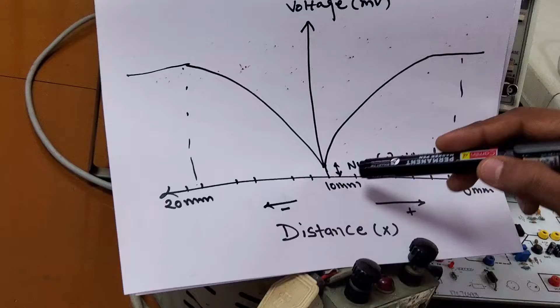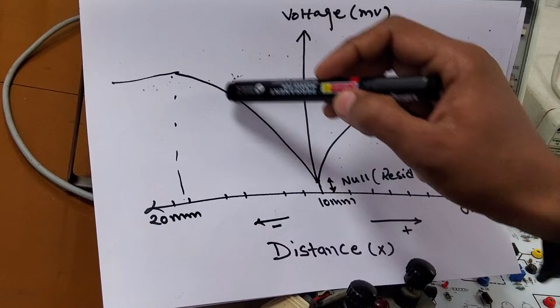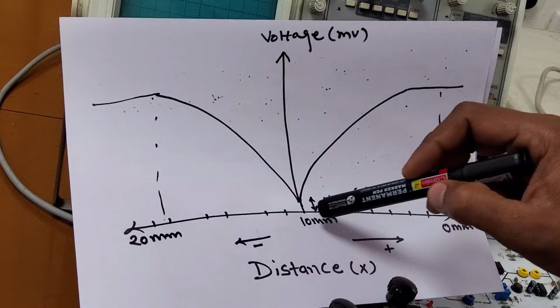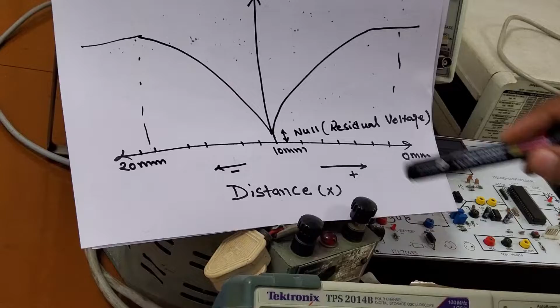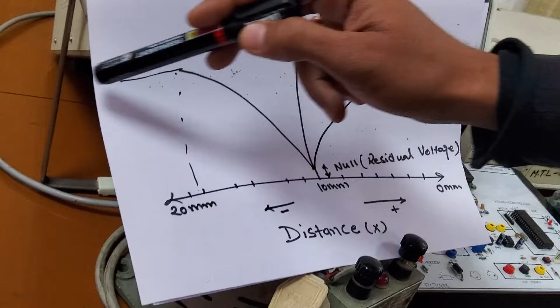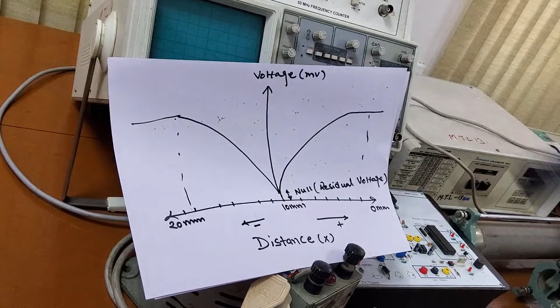So if you draw the waveforms, when we centralize the armature and move it to the left side, the voltage increases but stays positive. Now you see, if you move the distance from 10 mm to 20 mm, we get a waveform like that. If you increase the armature beyond 20 mm, our core is saturated, so we get a maximum output of 1 volt. This is how the waveform appears in our graph.